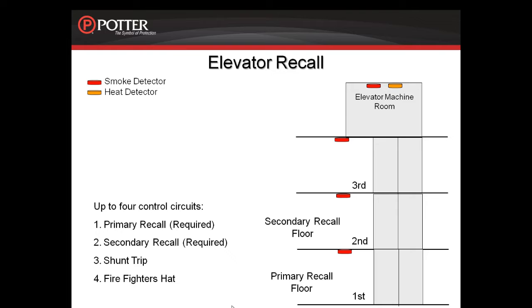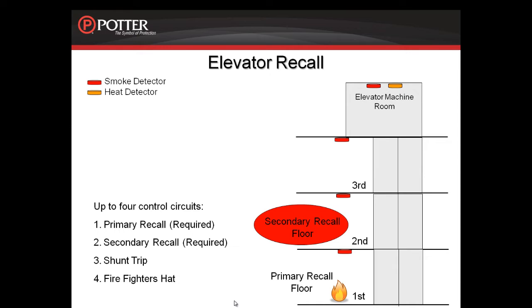In the event that there is a smoke detector active that is on the second, third, or any floor above that, we want to activate the primary recall relay, which will tell the elevator controller to recall the elevators to the primary floor of egress, which is in this case the first floor. In the event that there is an incident on the first floor, which is our primary recall floor, we need to recall the elevators to the secondary recall floor, which in this case is the second floor. So when the smoke detector on the first floor activates, we activate the secondary recall relay.